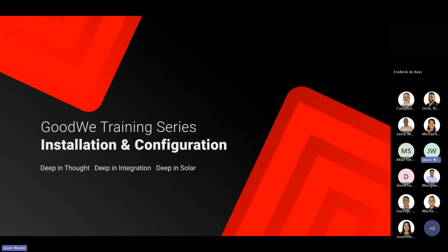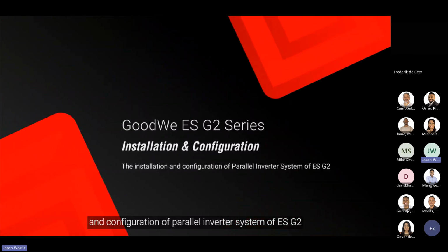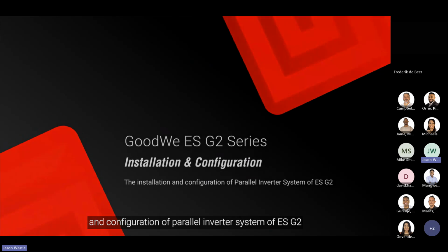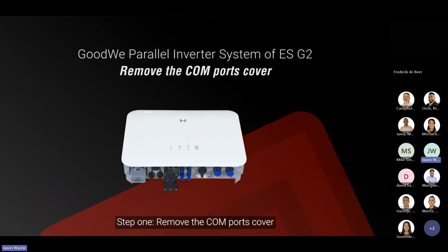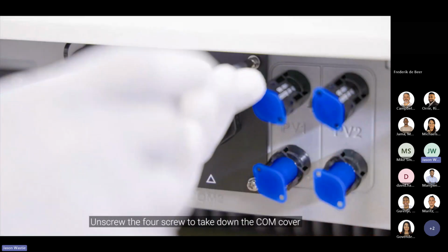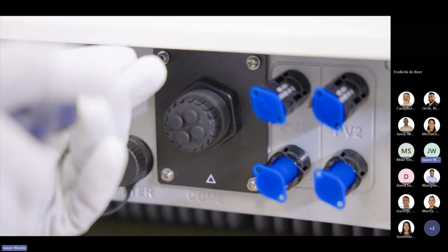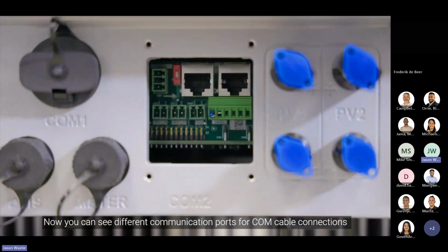Welcome to the GoodWe training series. Today we will take you through the installation and configuration of the parallel inverter system of ES G2. Step 1. Remove the COM ports cover. Unscrew the 4 screws to take down the COM cover. Now you can see different communication ports for COM cable connections.